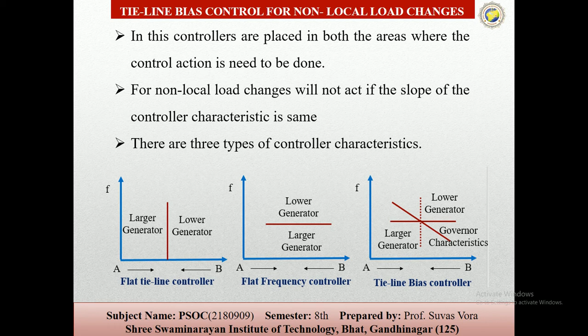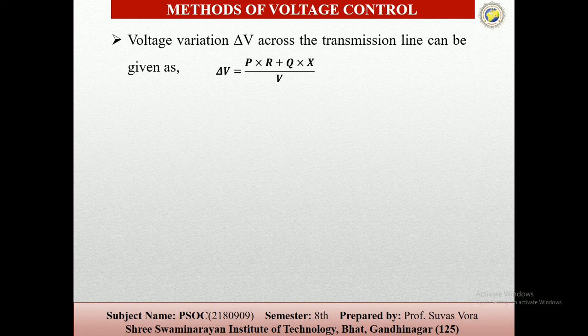Now the next topic is the method of voltage control. For satisfactory operation of motors, lamps and other loads, it is necessary to have constant voltage, and the voltage variation allowed is 10% as per IEEE standards. The voltage variation, delta V, across the transmission line can be given as delta V equals P into R plus Q into X upon V. Here delta V is the change in voltage, P and Q are the active and reactive power of the generators, X and R are the reactance and resistance of the transmission line connected to the generators, and V is the nominal voltage at the sending terminal.